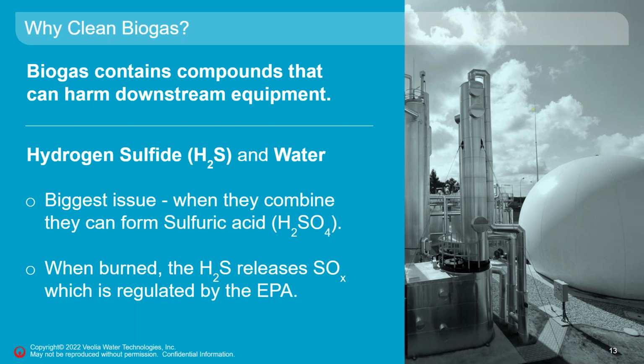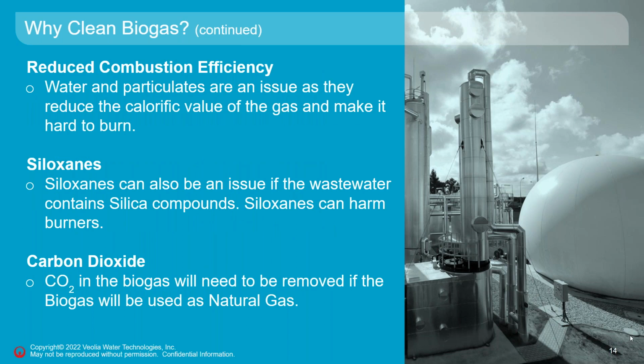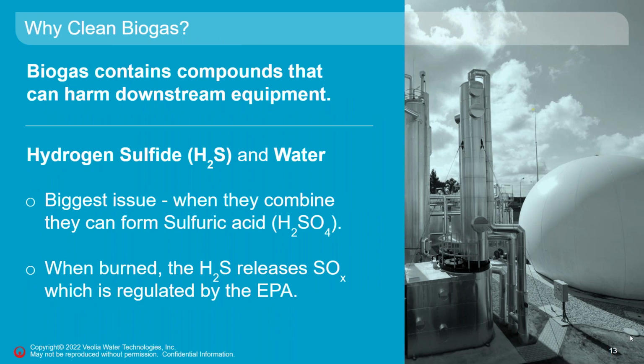And again, normally H2S is there in your biogas stream. So even when you burn it in your waste gas burner, it produces SOx gases like sulfur dioxide and sulfur trioxide, which is regulated by EPA. So a lot of times, even to burn biogas in the burner, you have to scrub out H2S first. Next slide, please.